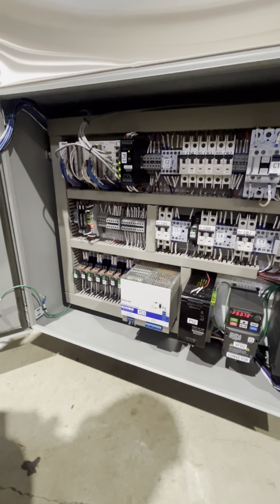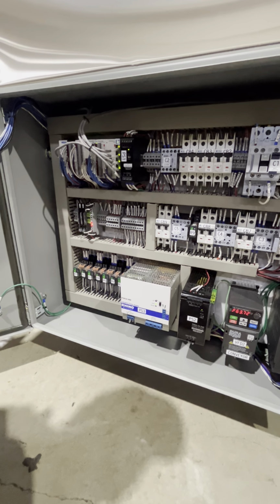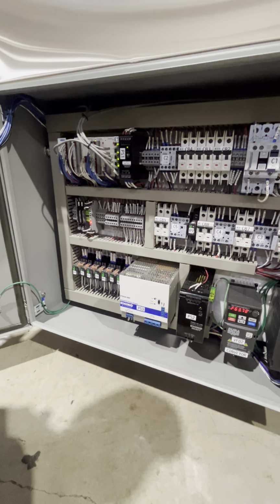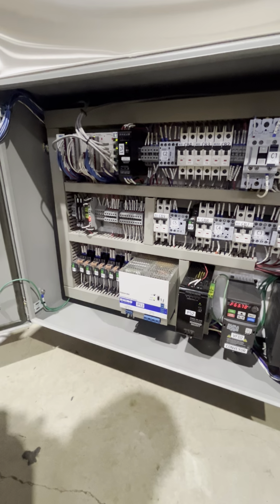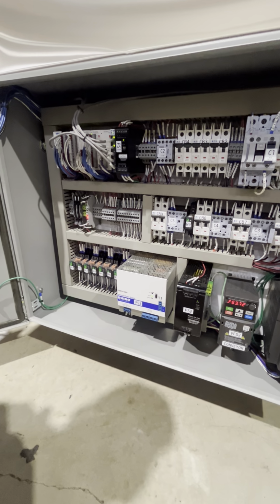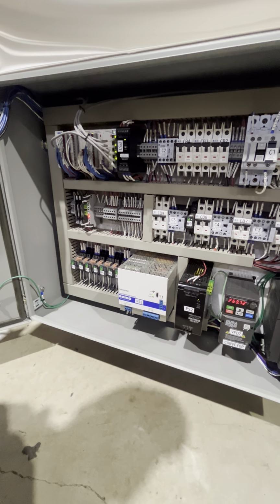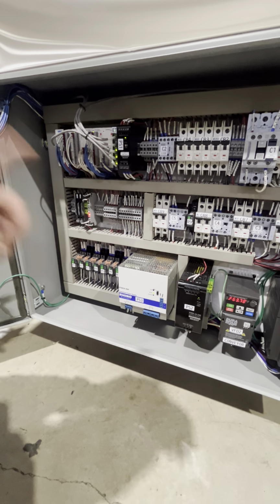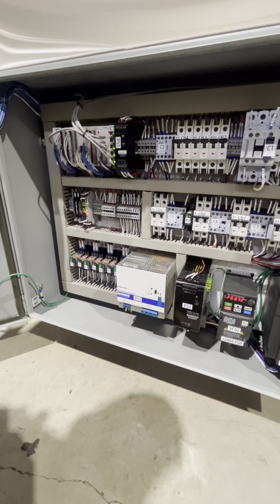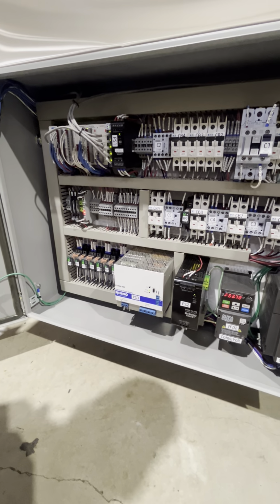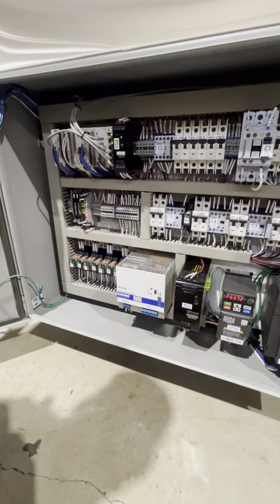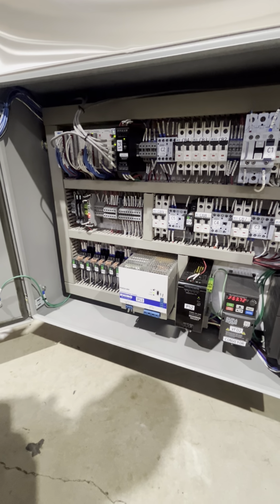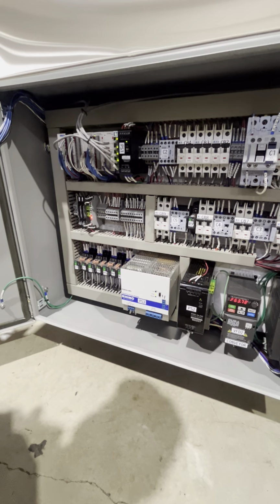Down here, the power supply that we have is primarily for the linear actuators. The linear actuators are 24 volt DC. Most of them max out at 10 amps. So this is a 40 amp output. We have 4 linear actuators on this module. In the others, we'll take a brief look at them as well. They all have individual power supply for the linear actuators.